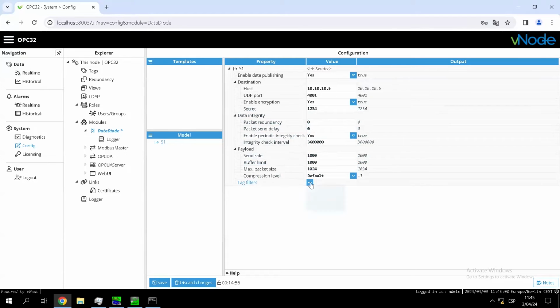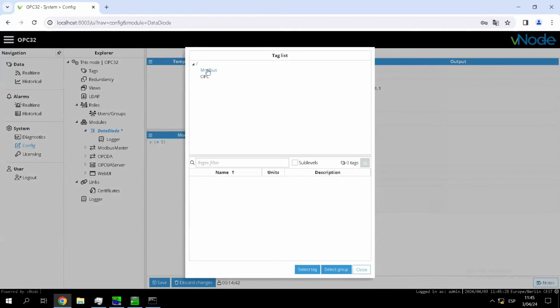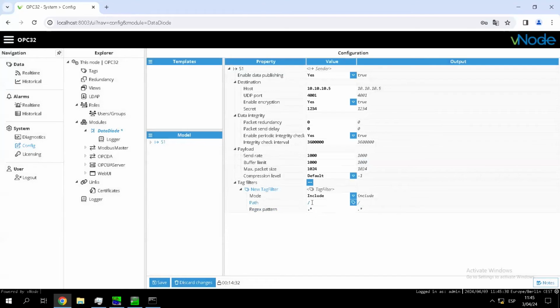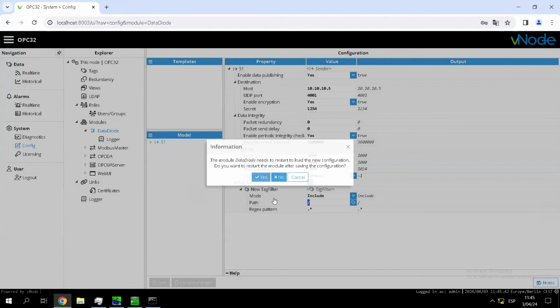Then we need the tag filters, which is the list of what tags I want to send to the other side. Maybe I have 50,000 tags here and only want to send 100 to the other side. So I can make filters and select whatever I want—only Modbus, only the OPC folder with all its tags, only one tag, or in this case I'm going to select everything. The slash means everything, so I press save, and that's it.